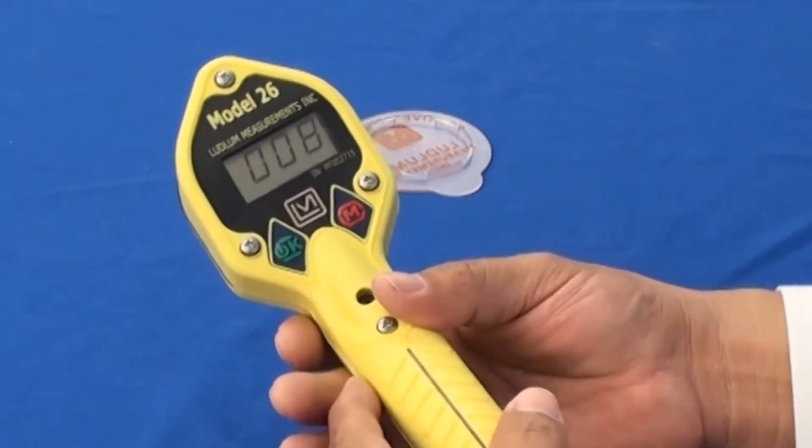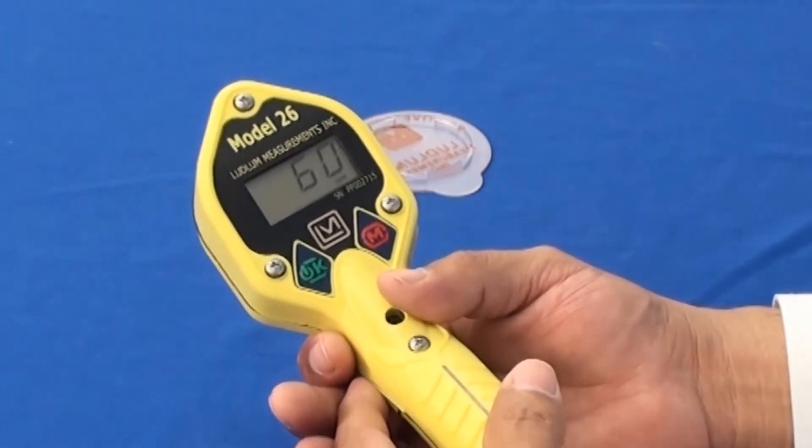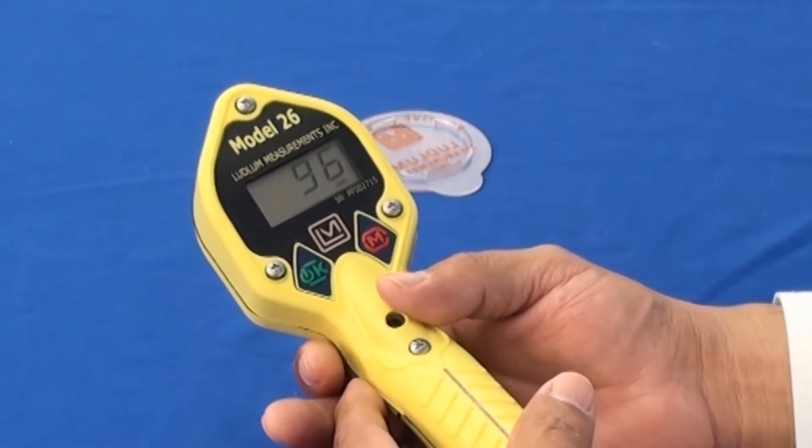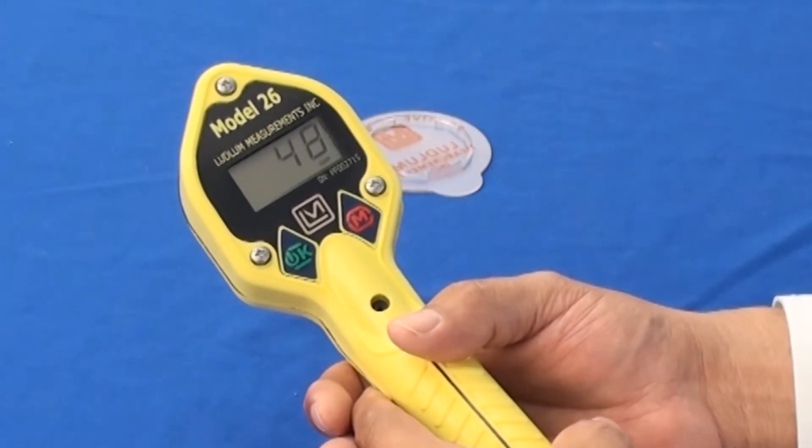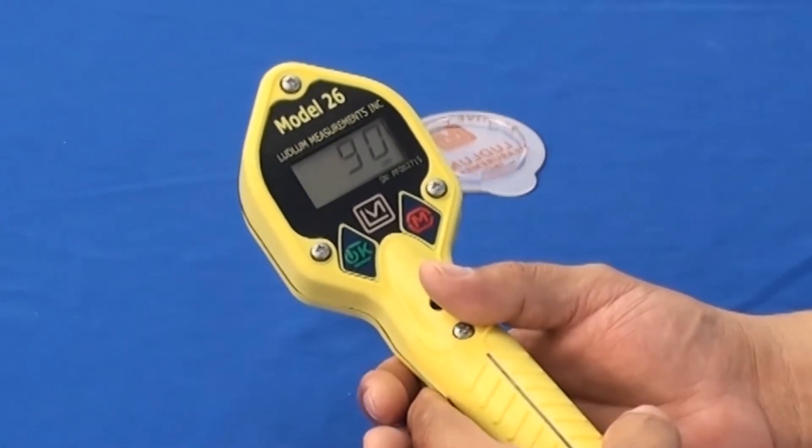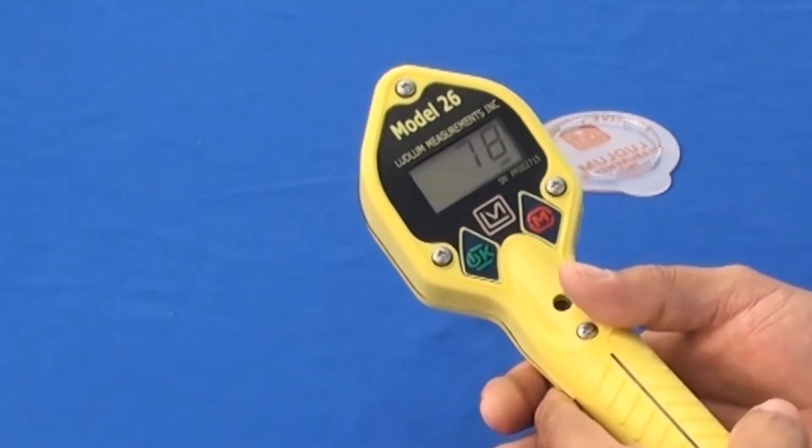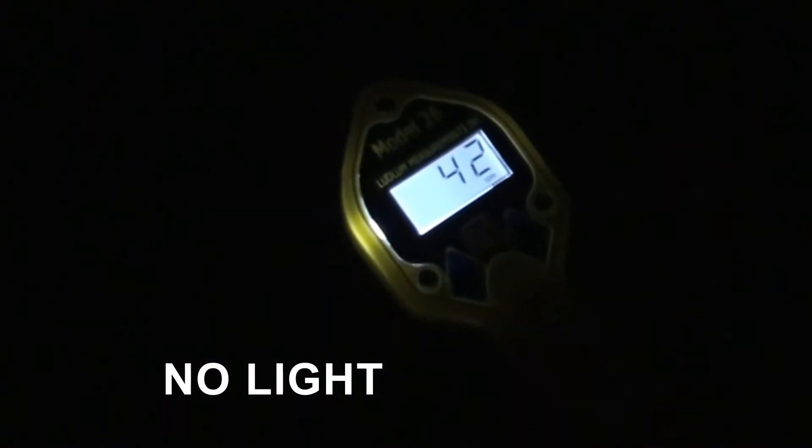The model 26 has a backlight feature that engages when you go to low light or no light in a situation where you're having to do a response check or a set of readings and you don't have enough light to visibly tell what's on the display. The backlight will engage on its own automatically and disengage once you're back into normal lighting. Here as you can see on the display of the model 26, the backlight has engaged and allows you to easily read the display.